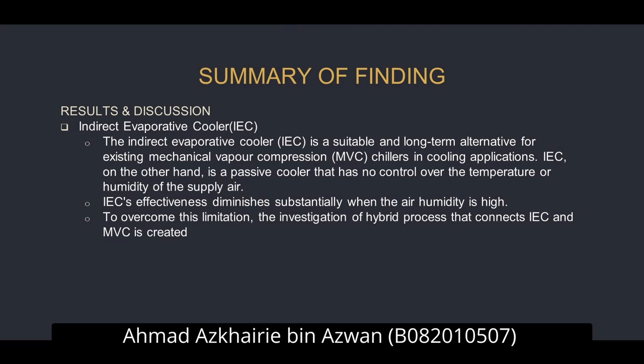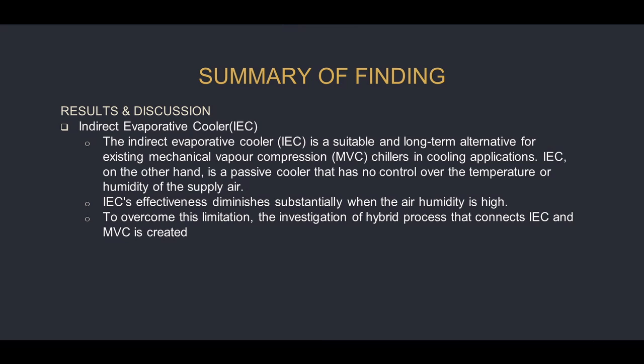Summary of findings, results and discussion. Indirect evaporative cooler (IEC) is a suitable and long-term alternative for existing mechanical vapor compression (MVC) chillers in cooling applications. IEC, on the other hand, is a passive cooler that has no control over the temperature or humidity of the supply air. IEC's effectiveness diminishes substantially when the air humidity is high. To overcome this limitation, the investigation of a hybrid process that connects IEC and MVC is created.